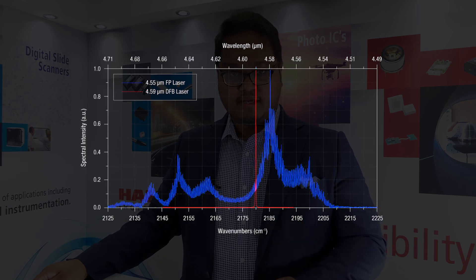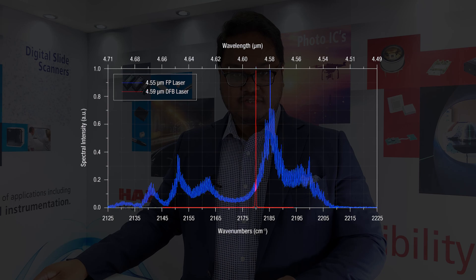However, oftentimes when you think of a laser, you might think of single mode — one specific wavelength of light emission. Actually, that's not the case with this kind of raw QCL. The emission is actually quite broadband, like the blue line here. For anyone performing high resolution spectroscopy, you can imagine that it's not really suited. However, we take this one step further and create a sharp red line of emission by creating a neat structure within the chip. We create a Bragg grating on the chip and the spacing between each grate determines the single mode the QCL will emit at. This isn't a filter — all of the wavelengths actually get fed back and produce a single wavelength.